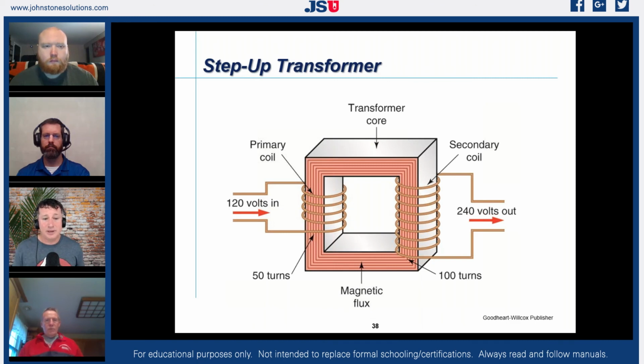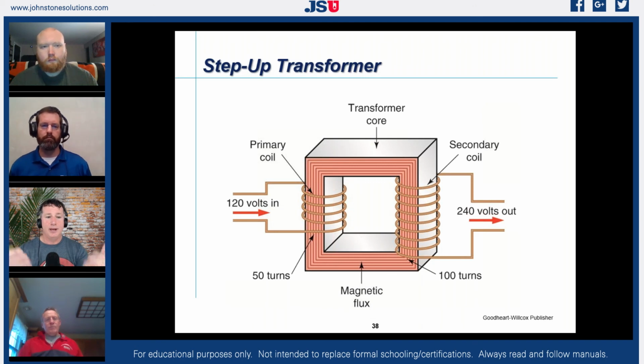We actually do that in my transformer class—we take a burnt transformer and figure out which winding failed, because typically you're only going to burn up one of them and the other is still going to be intact. That's a good way for you to understand exactly what we're showing here.